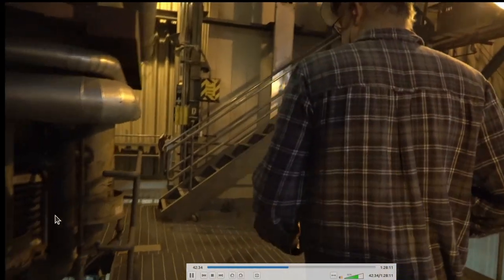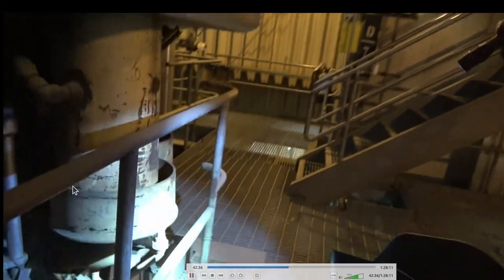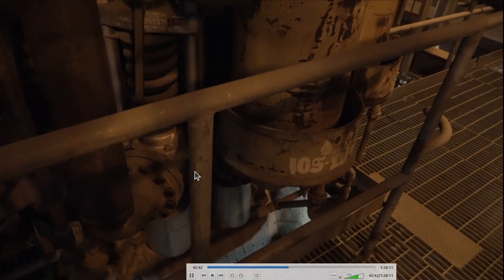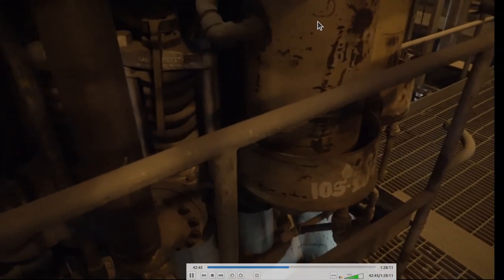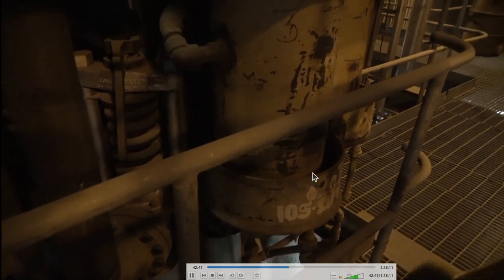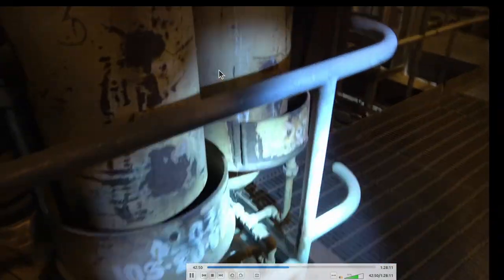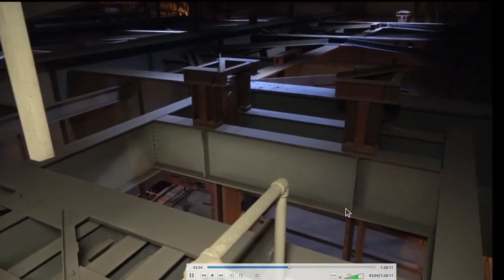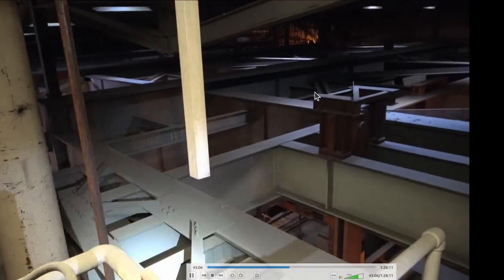That's the top of the boiler. The whole boiler is hung off the beams on top. Another set of boiler safeties — every year these are tested. I think they're set for around 2,900 PSI. This is the top of the boiler — you can see the hangers going down there holding up the steam drum and all the different tube sections.